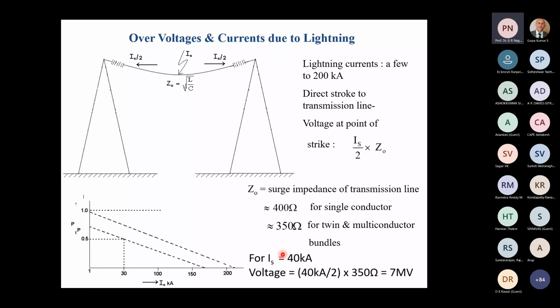Let's consider the other extreme. No ground wire. Therefore, the stroke has hit directly the middle of a phase conductor here. Here the surge impedance of the line is to be considered. As I told you earlier, it's root of L by C. It's not the resistance or the inductance alone. It has to be surge impedance. Typically, for phase conductors, it's of the order of about 400 ohms for single conductors, 350 ohms for twin and multiple conductors. So if you consider a 40 kiloampere stroke, 50% probability value, it divides into two parts between these two sides of the phase conductor. So 20 kiloamperes in each direction.